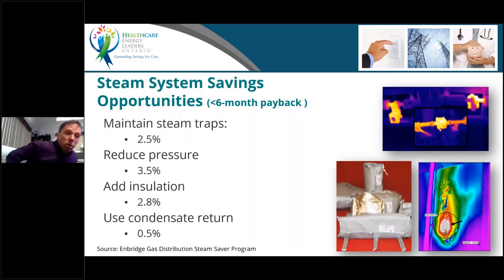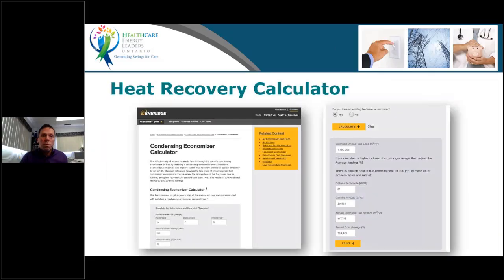Something we haven't talked about is condensate return. When you have a steam heating system, you don't actually use the steam. It's not direct steam use. It condenses into water. That water should be returned to your boiler plant so that you don't have to use fresh water that's cold. So you have this warm, hot condensate returning to your plant that is used as your boiler feed water. Here it shows a heat recovery calculator for a condensing economizer.